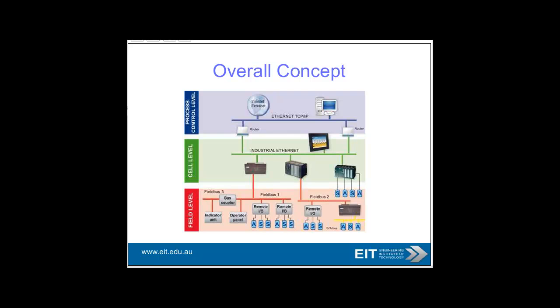Down at the field level, you don't really see TCP/IP at this stage, although in the future you probably will see more of it. But at the moment, you see fieldbus and DeviceNet. For obvious reasons, fieldbus — for example in an intrinsically safe area — you probably need a Foundation Fieldbus solution or a Profibus PA solution. With RS485, you can't really send it to those areas. And then at the cell level and the level above, industrial networks need TCP/IP, and then obviously at the control level, also TCP/IP.